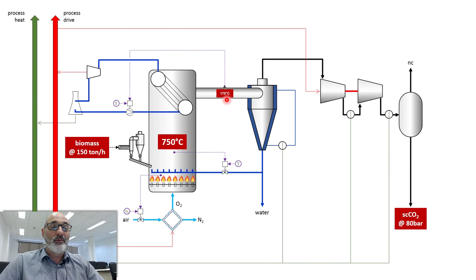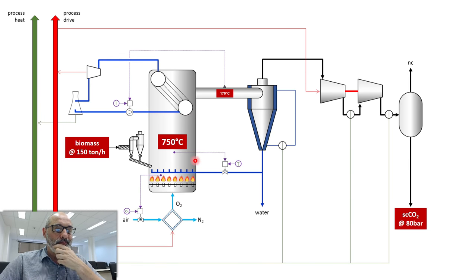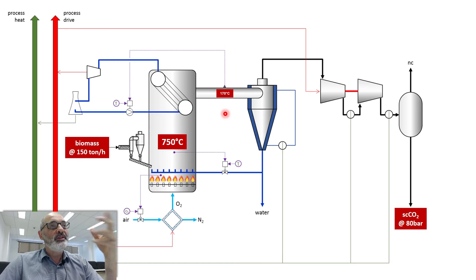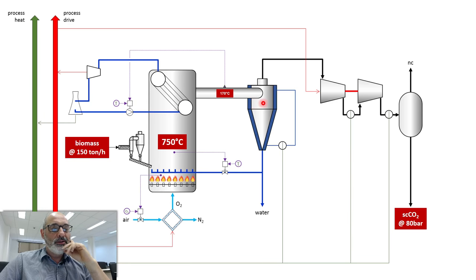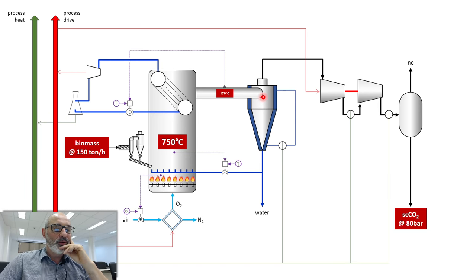We have hot gases at 170 degrees. If we are burning with pure oxygen, we're going to have CO2 and water only — we don't have nitrogen. There are contaminants and other non-condensibles, but they are negligible in terms of the energy balance. In this oxy-fuel process, we supposedly have pure CO2 and steam. What we need to do next is dewater the gases. This is easily done by further cooling the process — by doing this, water condenses.